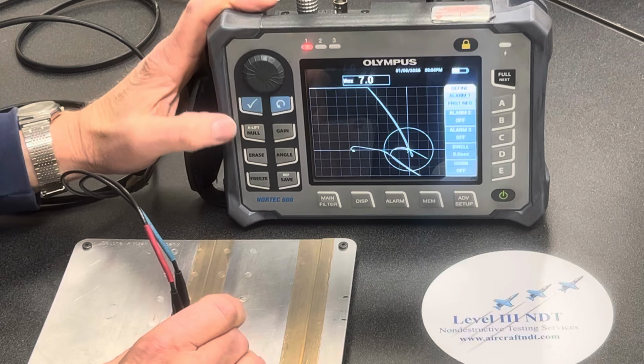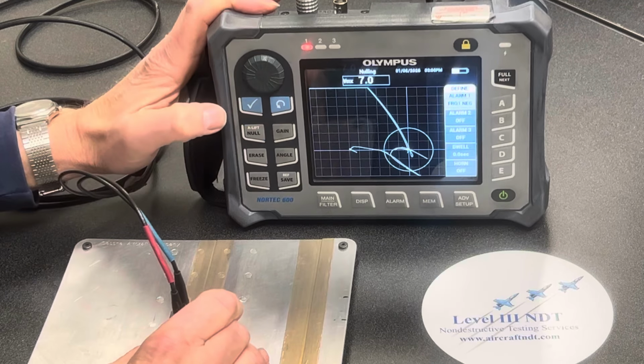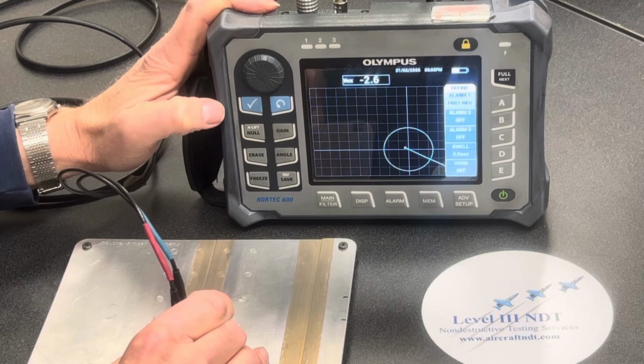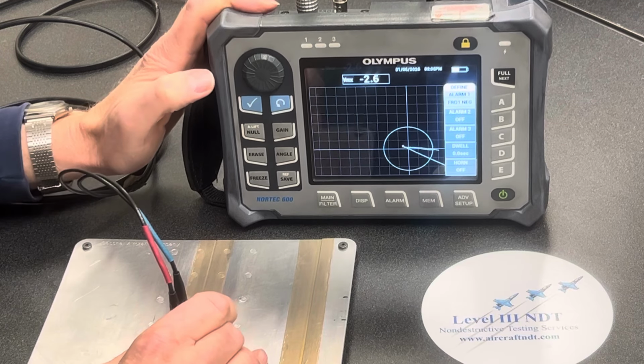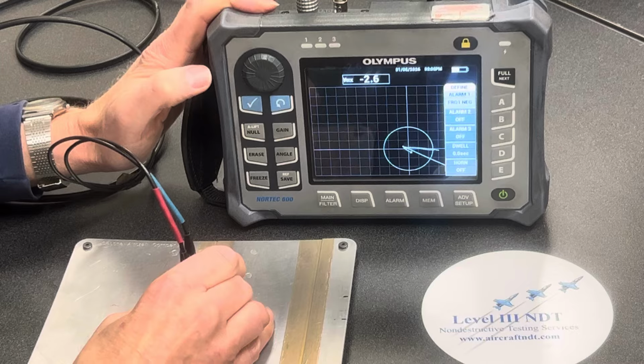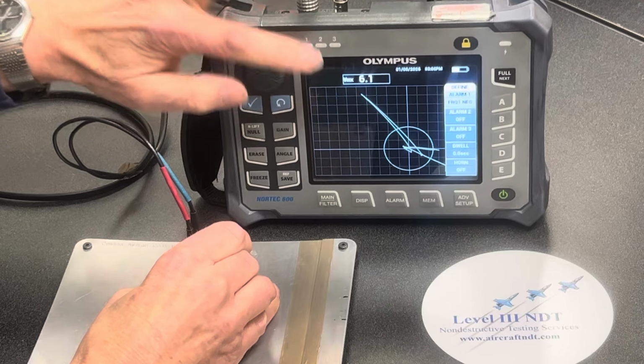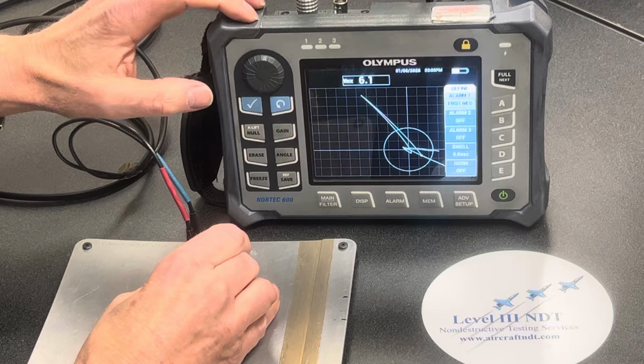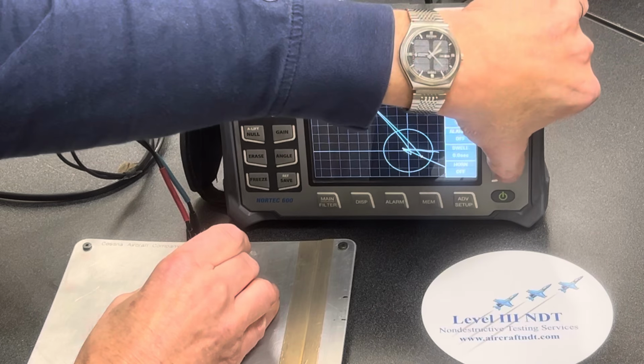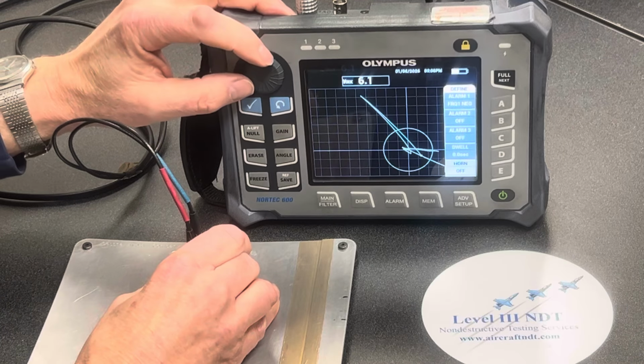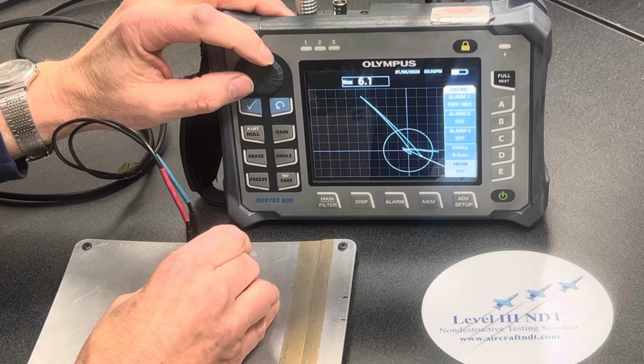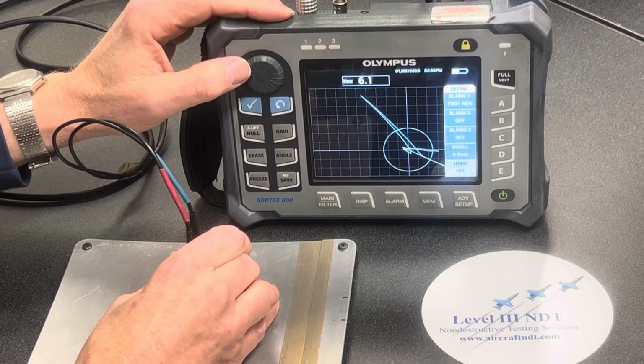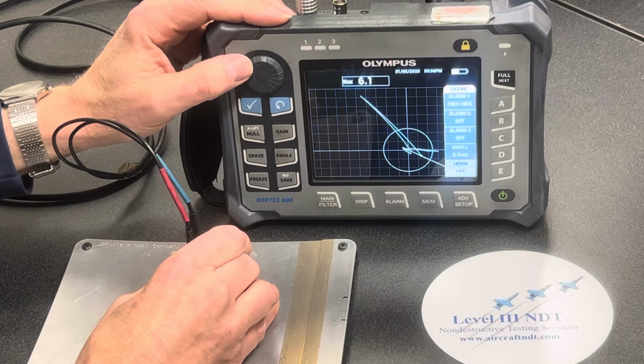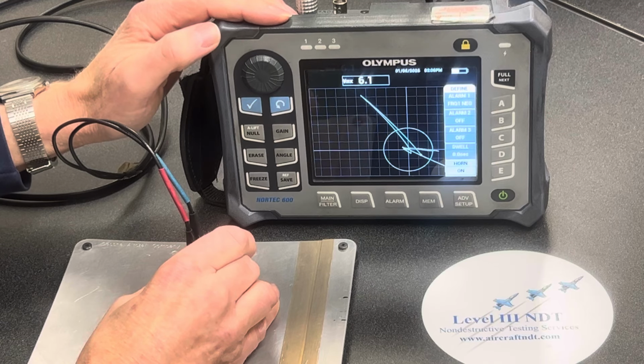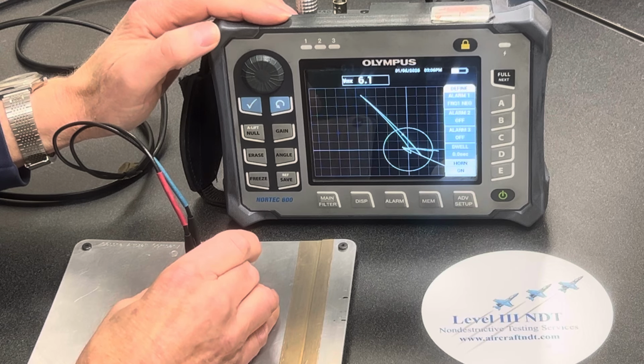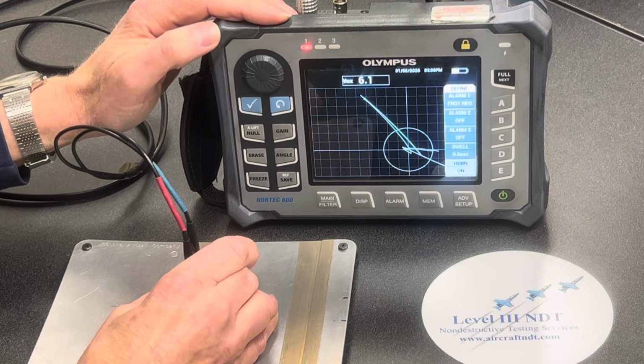We're going to go ahead and null the instrument. Check our alignment again and our liftoff, and go over our EDM notch. Again, we're over 6 on vertical, so we're good. And the last thing we want to do is set an alarm horn, so that if we're looking at the aircraft and the dot goes outside of the screen, not only would we see it on the screen, but we can hear it audibly. So the alarm horn is set to on, but we only will hear it if the dot goes outside of the polar alarm.